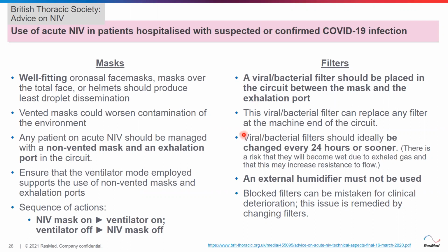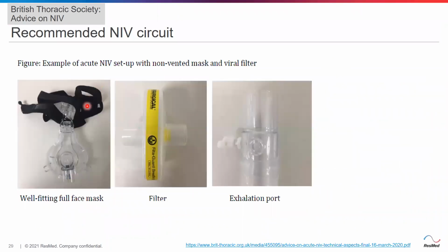Fine. And which would produce an unnecessary impedance or resistance to the flow of gases. Fine. So that's why every 24 hours the antibacterial or viral filter should be changed. Fine. An external humidifier must not be used since it increases the risk of aerosolization. Fine. So this is the recommended circuit.